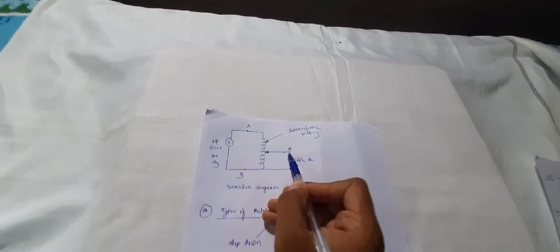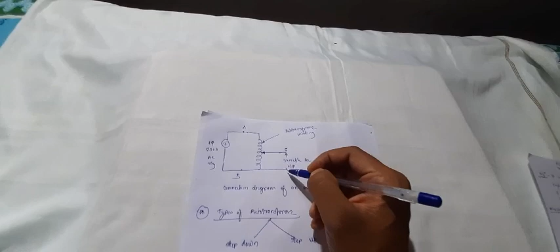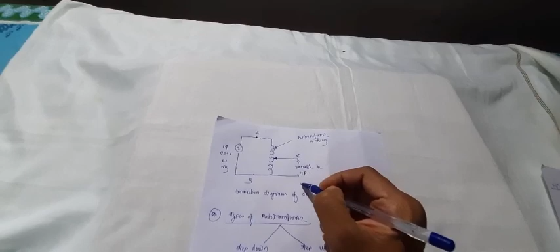We'll take the movable terminal out with respect to terminal B or ground; this is our secondary side. So this is the primary side and the secondary side. We'll apply input here between the primary terminals and apply load between the C and B terminals.